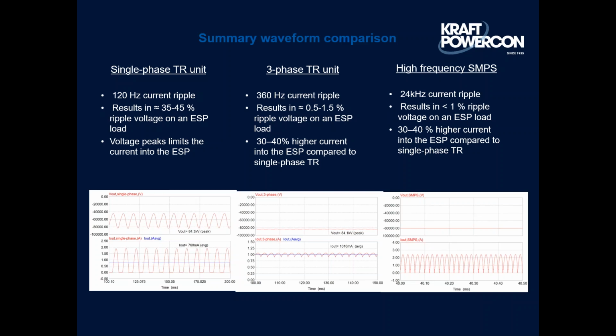Kraft Powercon was actually one of the first with this technology in the 80s. We also worked with Flakt Alstom in developing the SMPS technology in the 80s. But Kraft Powercon was having a difficult time maintaining our reliability philosophy on the SMPSs, so we abandoned that technology for a while and stuck with the 3-phase TR set. Our philosophy at Kraft Powercon is that a precipitator shouldn't be worked on all the time, you turn it on, do your maintenance, and forget about it until the next outage. The SMPS was a more complicated technology.